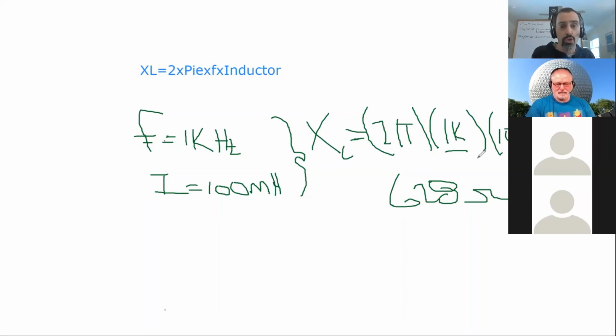So you can have a short circuit inside. The short will actually cause the henries to change because you now no longer have the same amount of turns. The second thing is you can short it out, open it up, and then you get nothing on it. So there's two things that possibly would happen. Number one is more likely than number two. And when that usually does happen, you get a very high increase in current, because remember, your ohms is changing. So your current's going to react to that and bounce up.